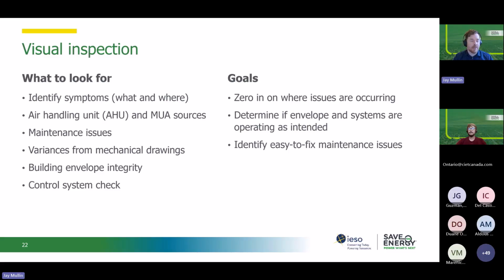And lastly, doing that visual inspection of the control systems, whether that is a BAS or local controls. You want to be looking at whether interlocks between makeup air and exhaust are enabled and working. Are fans following correct schedules? Are building pressure sensors calibrated and functional? Are economizers working as intended? Are damper positions accurate? Are VFD set points appropriate, and are alarms in place and working as intended, like burner lockout and damper faults? Are all those alarms clear? Is the outdoor air minimum flow set correctly and not too low? So you want to check all of those.